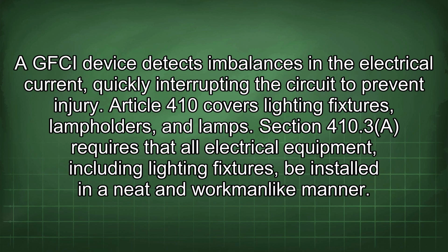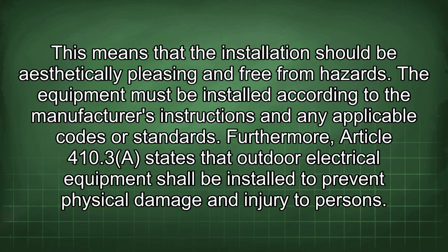Article 410 covers lighting fixtures, lamp holders, and lamps. Section 410.3 requires that all electrical equipment, including lighting fixtures, be installed in a neat and workmanlike manner. This means that the installation should be aesthetically pleasing and free from hazards. The equipment must be installed according to the manufacturer's instructions and any applicable codes or standards.